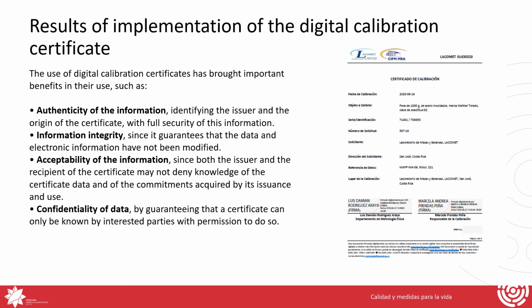The use of digital calibration certificates has brought important benefits, such as authenticity of the information, identifying the issuer and the origin of the certificate; integrity, since it guarantees that the data and electronic information have not been modified; acceptability of the information, since both the issuer and the recipient of the certificate may not deny knowledge of the certificate data and of the commitments acquired by its use; and confidentiality of data, by guaranteeing that a certificate can only be known by interested parties with permission to do so.